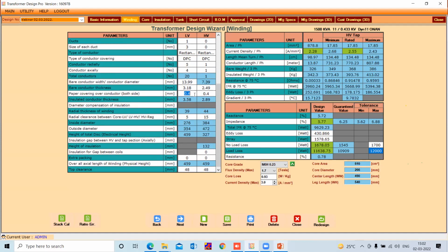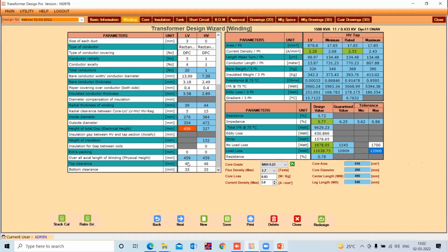Everything is editable. Whatever white backgrounds you see, you can change the values the way you want. You can see the radial thickness of winding, the radial clearance between them. That's again in white background. The inside diameter, the outside diameter, the total disc height, that's the electrical height. Then the height of insulation, then the extra packing if you wish to provide, the overall axial length of winding. You can also set the bottom and top clearances, and they are in the white background. That means all of that is editable.